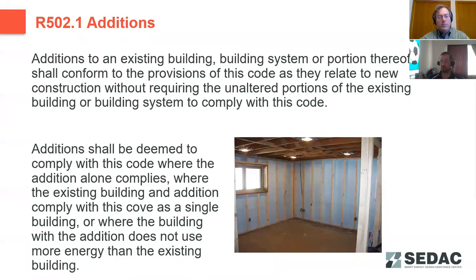However, if you want to do performance testing on the entire building and comply with the additions through a performance path method, then you are probably going to be doing pressure testing and duct leakage testing to maximize what you can trade off for that addition. But you have to show that your overall addition and original building is using less energy than the original structure.